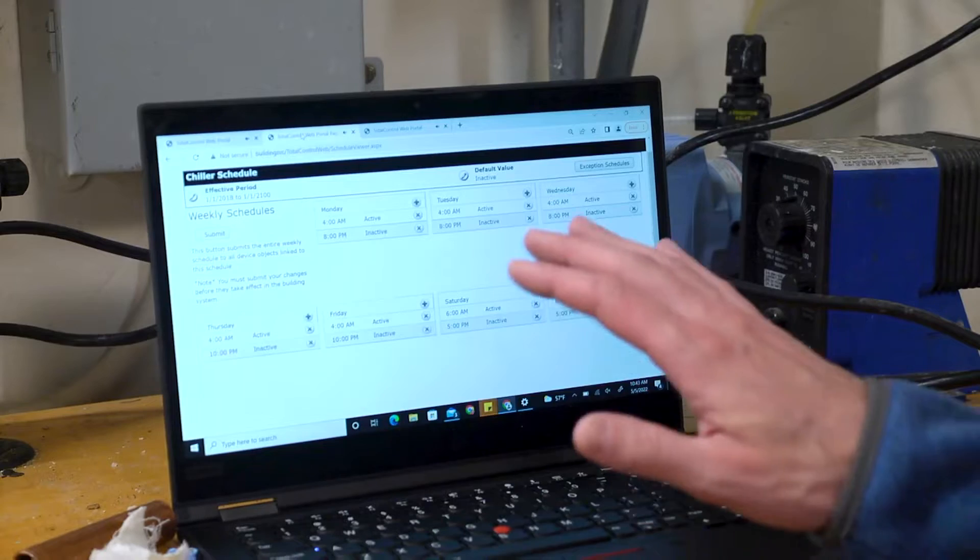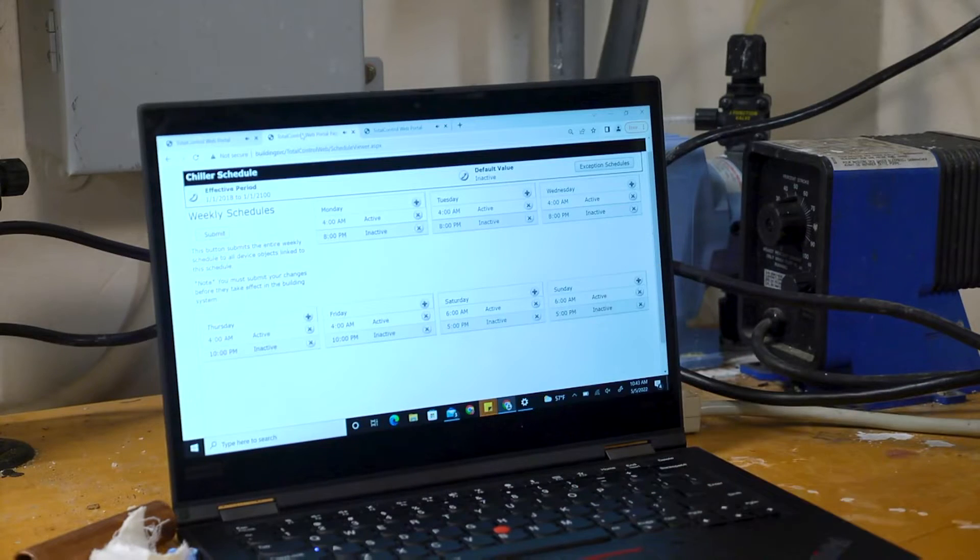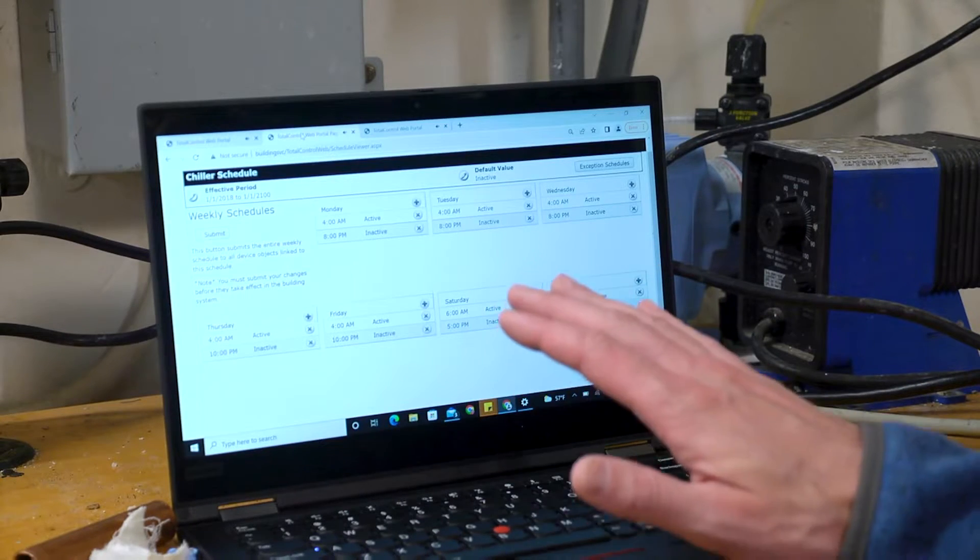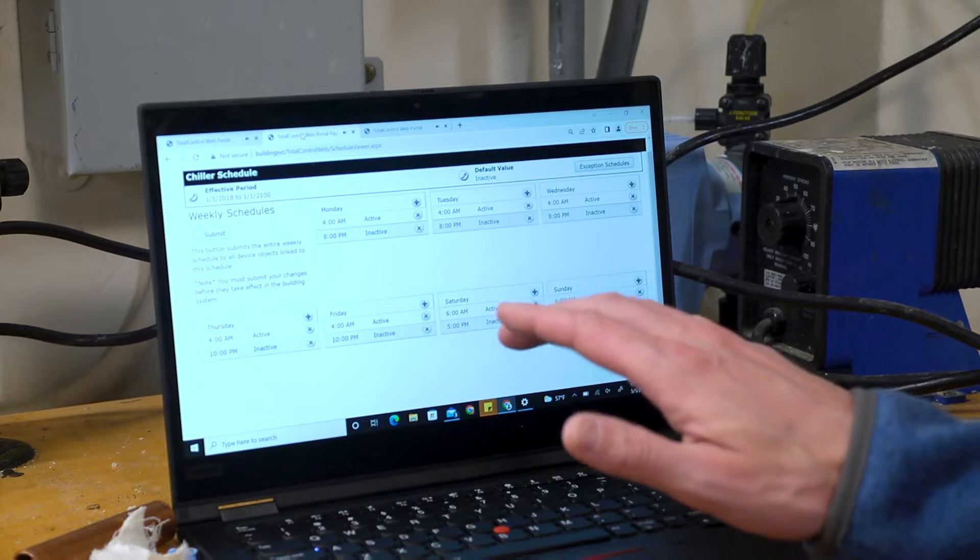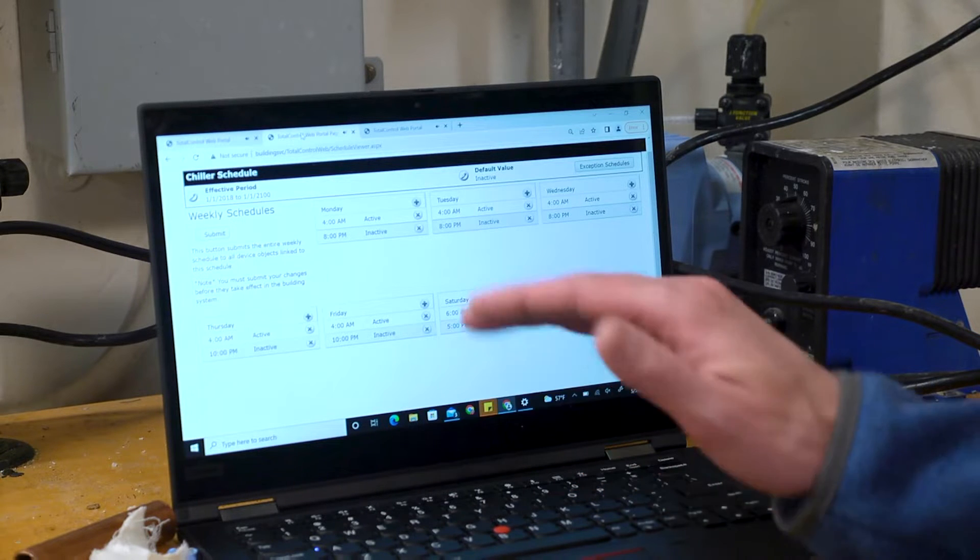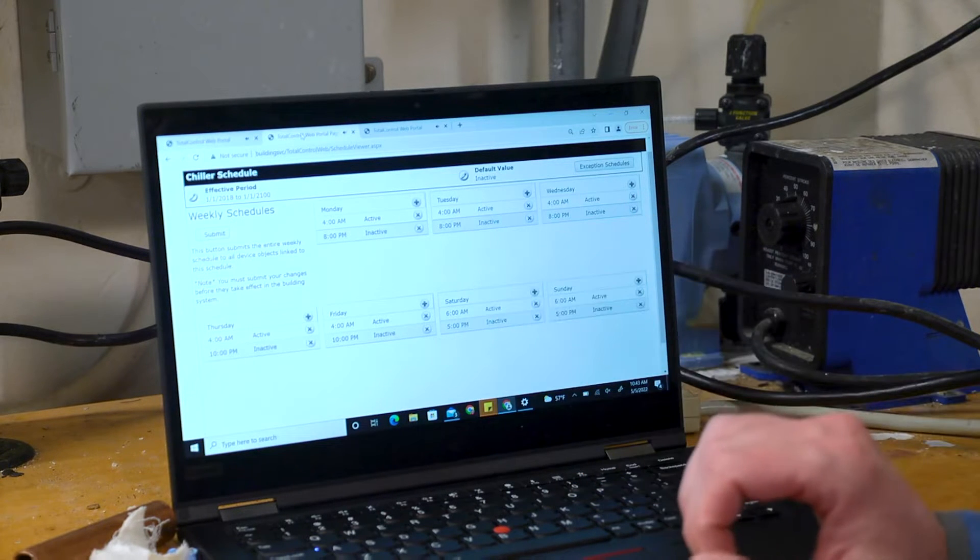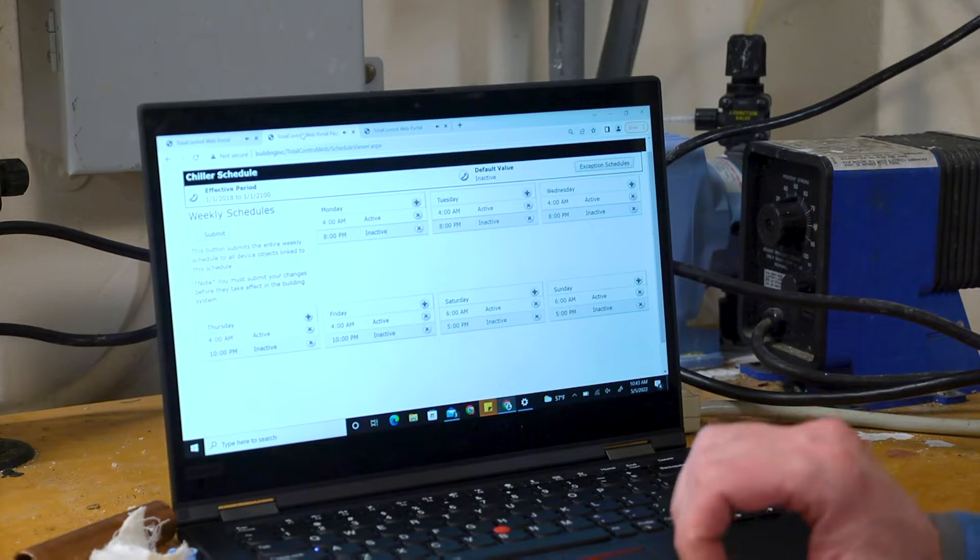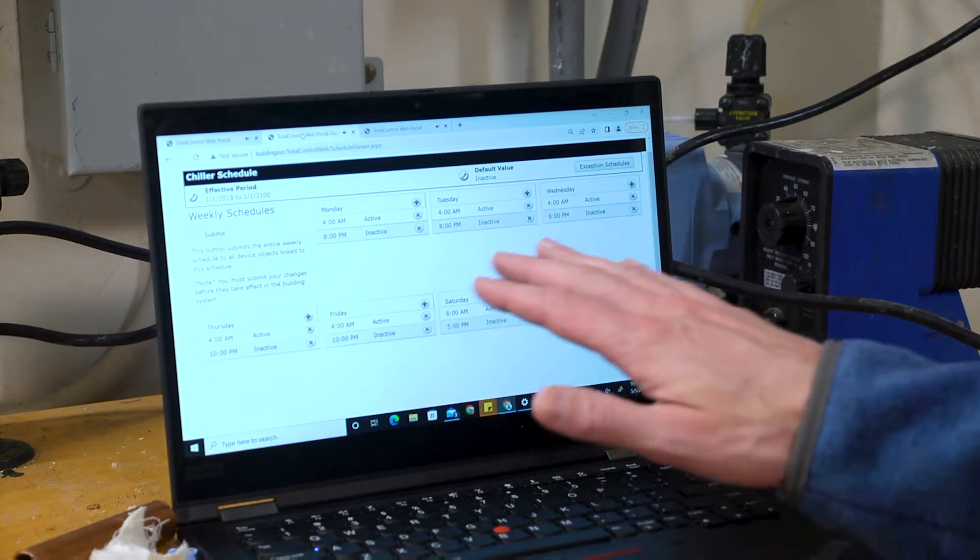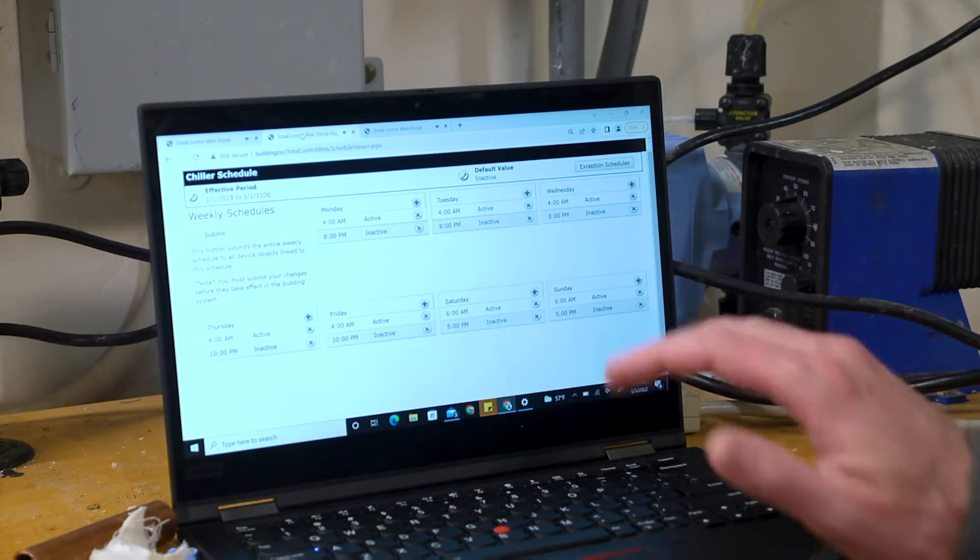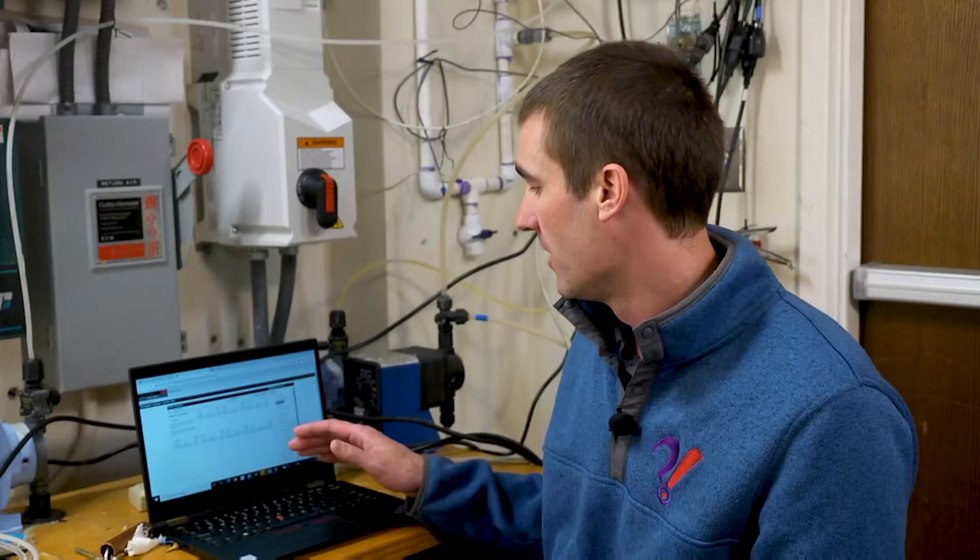It's on the building automation system that these can be configured. Take a look at it. In this particular case, we have a chilled water system. It's allowed to operate seven days a week to include Saturday and Sunday. That might be appropriate for this upcoming Saturday and Sunday, but there might be some Saturdays and Sundays in the future where this facility is going to be completely empty.